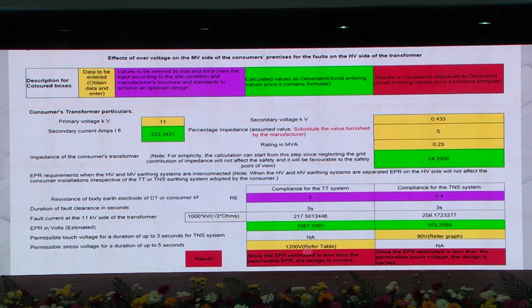And you can have 1200 volt easily managed by this 5 ohm consumer using the TT system. In the TNS system, we should have 0.4 ohms. It is possible in the TNS system, and this is the value that can be attained. For 0.4, it is not attained. Suppose you go to 0.3, if you go to 0.3, we can easily achieve this permissible touch potential. This is 101 volt at 3 seconds based on the previous graph.